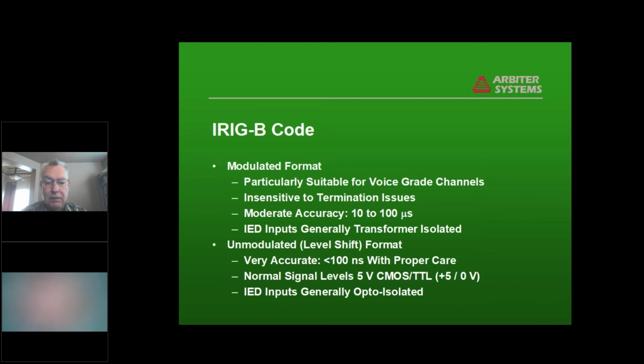The unmodulated level shift, or TTL format, is much more accurate. It has the same accuracy of 1 pulse per second. And again, IED inputs are generally opto-isolated. They use an opto-isolator or a digital isolator these days to break ground loops and protect the input of the IED from transients.